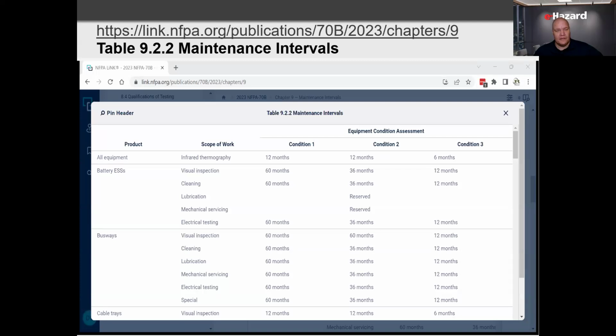That's where we get into the specific tables when we reach the specific chapters. Each chapter for specific equipment has like 4 or 5 tables, but there are 3 main ones: visual inspections, mechanical servicing, and electrical testing. In this table I've got visual inspection, cleaning, lubrication, mechanical servicing, electrical testing, and if there are any special tests specified in those chapters, I've got a section for that too. So you can't use chapter 9 without also using the specific chapter it applies to.